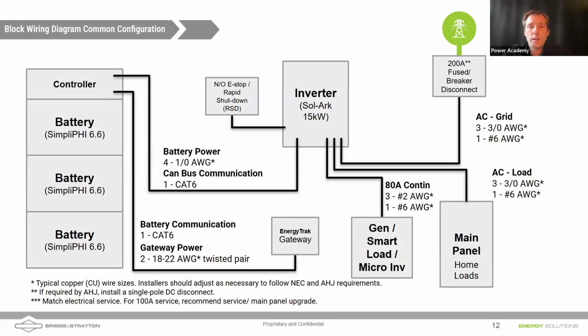The notable example here is that, hey, that Sol-Ark inverter now, all of the power from the utility is passing through the inverter, and that's passing through to the main load. So that's the example of 200 amps. Now, if we're off grid, instead of having the utility coming in with that 200 amps of pass through, you potentially could have a generator coming in with 200 amps of pass through. Notice that just one load center in this example, and this is what we're referring to as whole home backup.